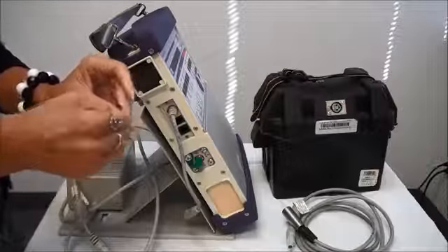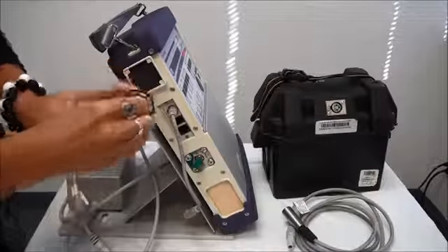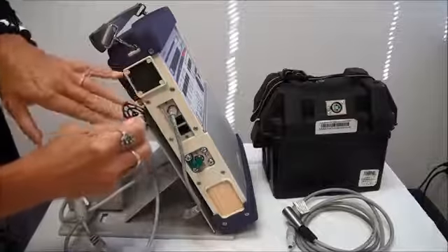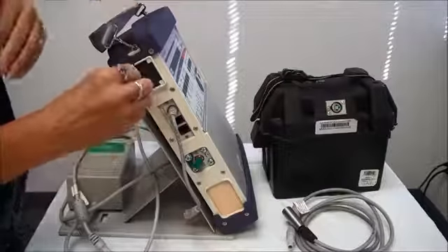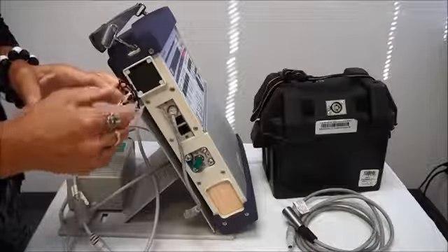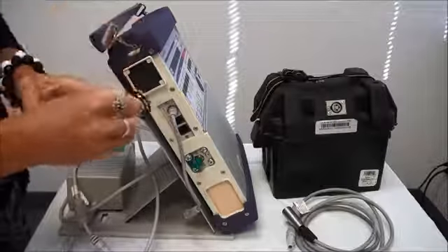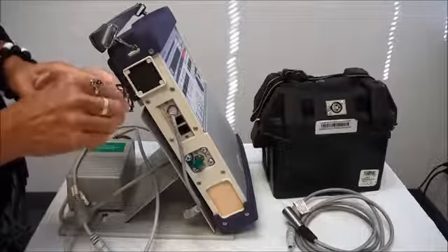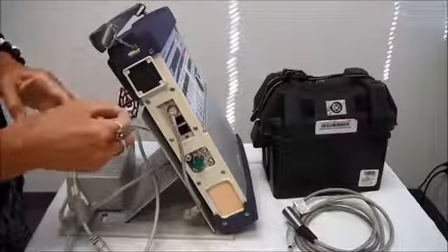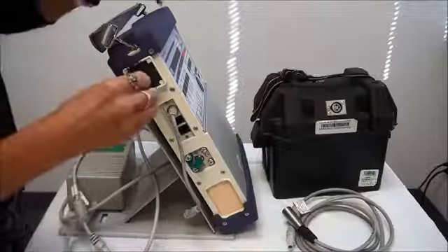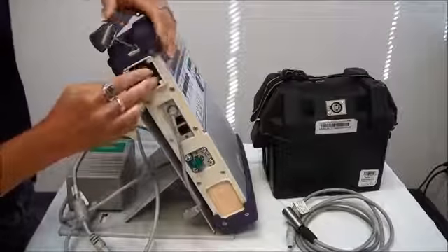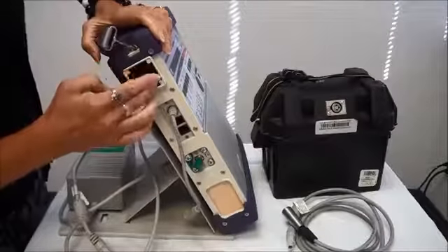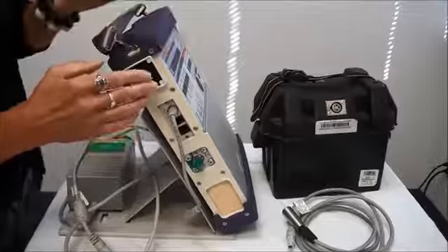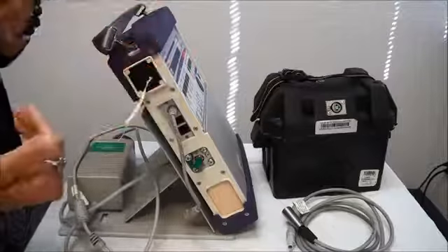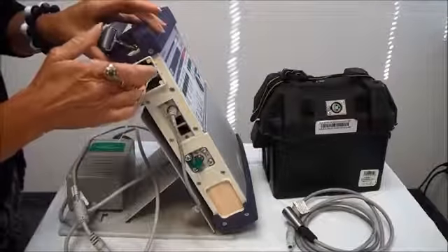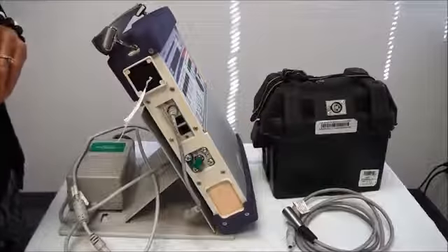The thing you want to take care is that you put the twist tie on while the cover is out of the ventilator. You never want to do this while the cover is in the ventilator, because then again you can poke something behind the filter and you can do damage to the ventilator. So this is just another tool to make it easier to pull this cover in and out. And then when you put it back in, you actually have to push on the sides and it will snap into place. If you don't do that, it's going to fit in there real loose and it'll pop out. So you have to snap it in so it fits in there nice and tightly.